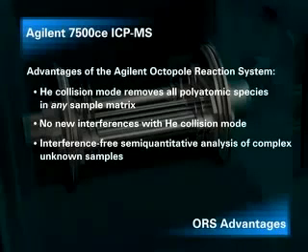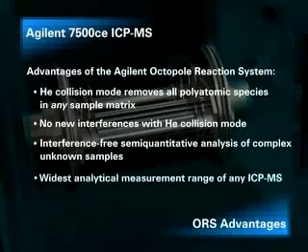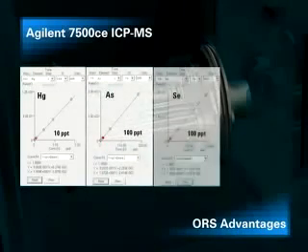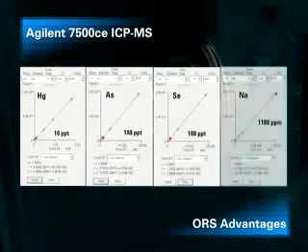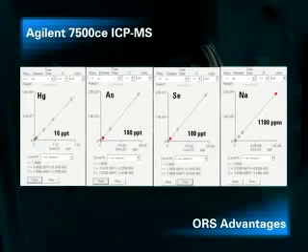More than 60 elements can be measured in a completely unknown sample in approximately one minute without the need to run calibration standards. The 7500 CE can measure mercury at single-figure parts per trillion plus sodium at greater than 1000 parts per million in the same analytical run. The calibration graphs show excellent linearity for mercury down to the 10 parts per trillion level, arsenic and selenium down to 100 parts per trillion, and sodium at 1180 parts per million — all achieved in the same run. The ability to measure elements over a wide concentration range in a single analysis clearly demonstrates the power of the ORS.